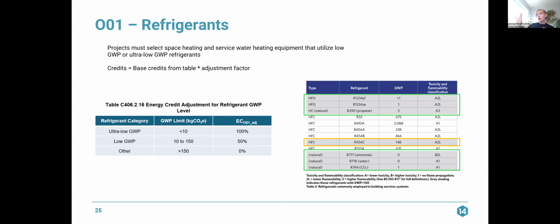I did pull down this chart that shows the type of refrigerants and their GWP as just like an easy reference. You'll see that if it is not in a box, it is not a low GWP or ultra low GWP refrigerant. The only low GWP refrigerant in this table is the R454C. That's at a 148. It is an A2L. You guys, I'm sure, have heard of all the talk about the A2L refrigerants that are required.